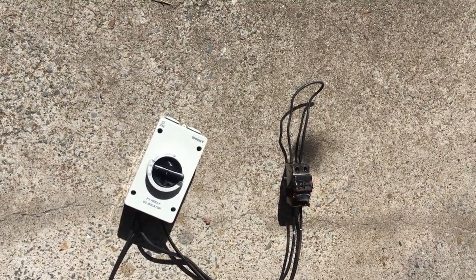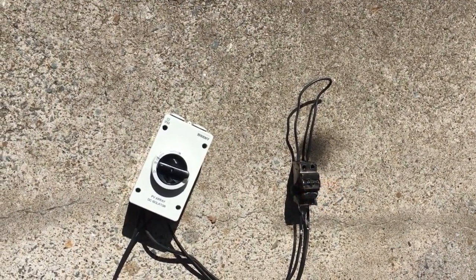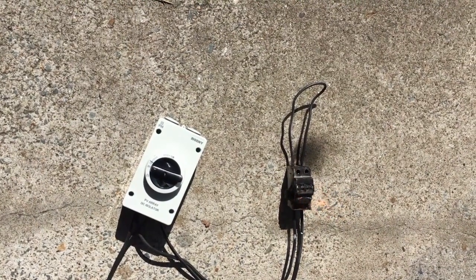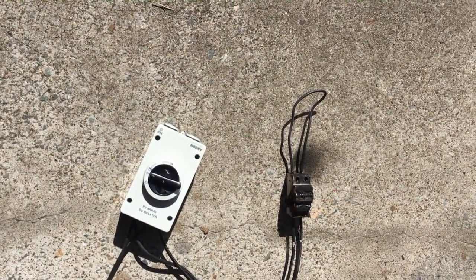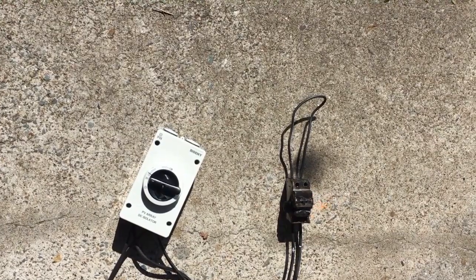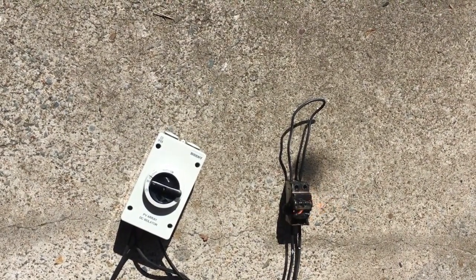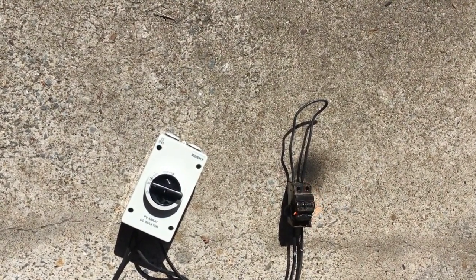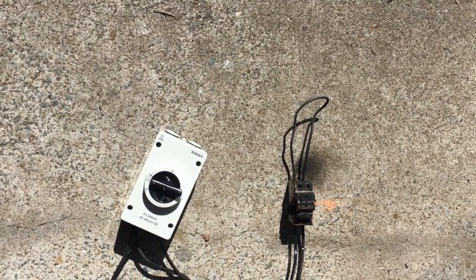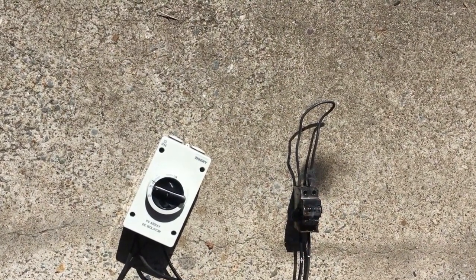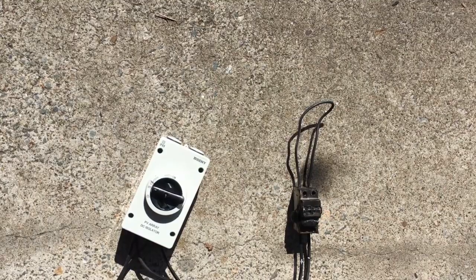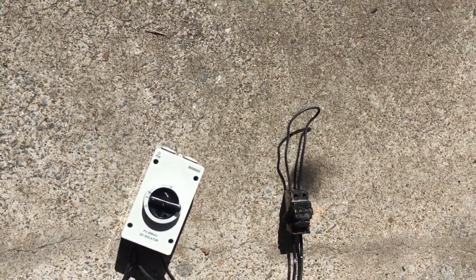However, we have been to many jobs which other people have done. The installers are no longer around, and we have at times seen these circuit breakers wired incorrectly like this. And look, when the system's all on and working fine, there's no problems. But the problem is, if the thing is turned off under load, you're going to have a situation like this happen to your circuit breaker.